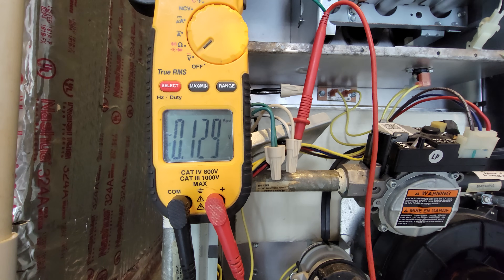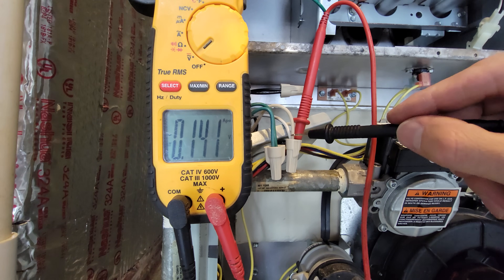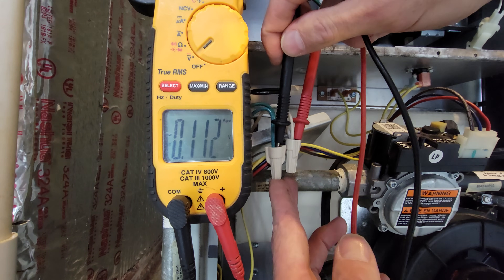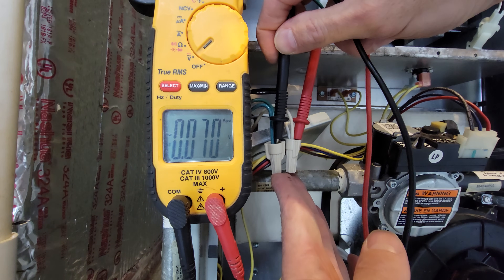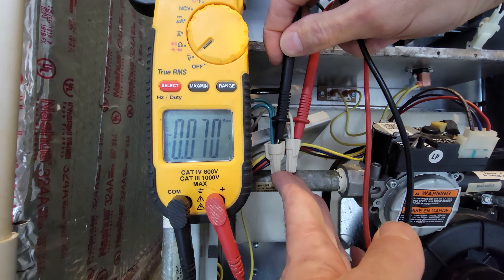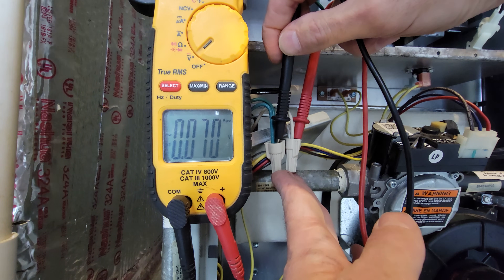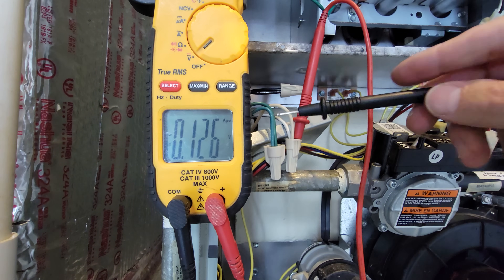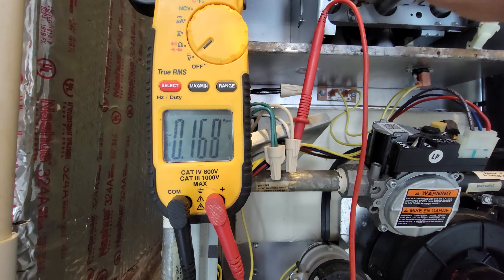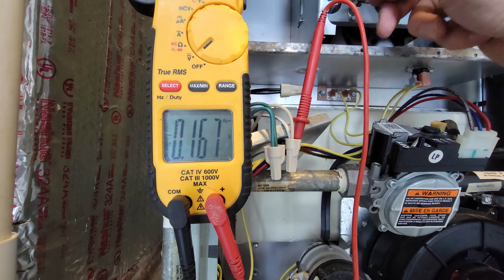To check a suspected flame rectification problem, check the ground wire. Set your multimeter to AC voltage and measure the potential difference between your common neutral wire and your ground — these two are connected in the breaker box, so there should be no voltage difference between them. We're measuring 0.07 volts here. If you were close to half a volt or a full volt, that would indicate a bad ground to your furnace. Remember, the flame rectification signal travels on the ground wire, so a problem with that ground means the control board may have trouble determining whether there is a flame.